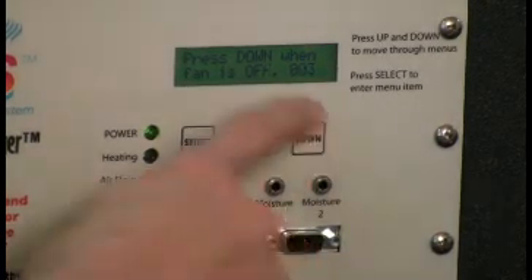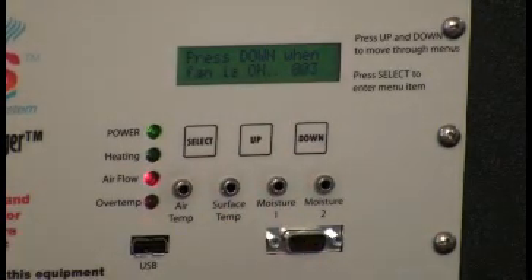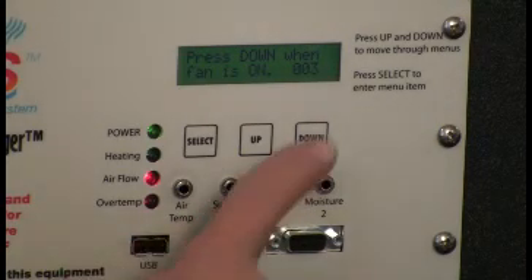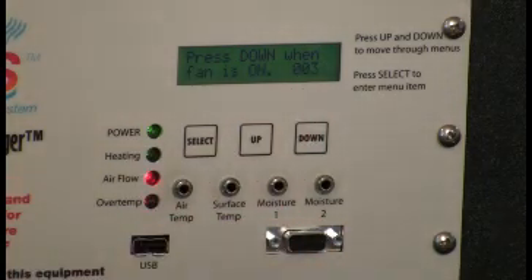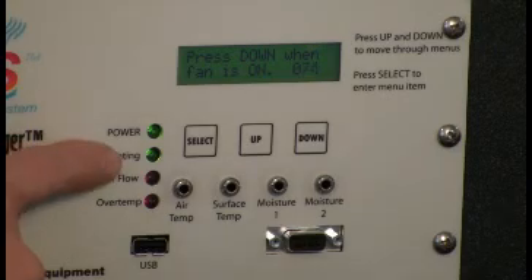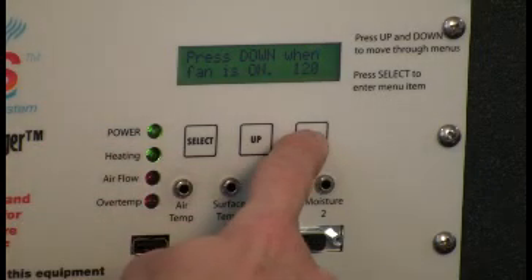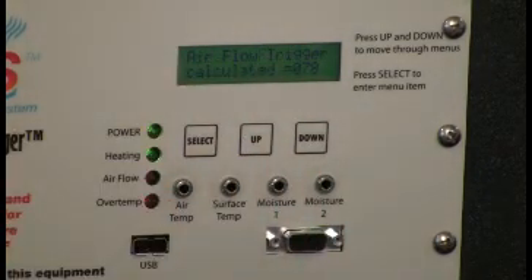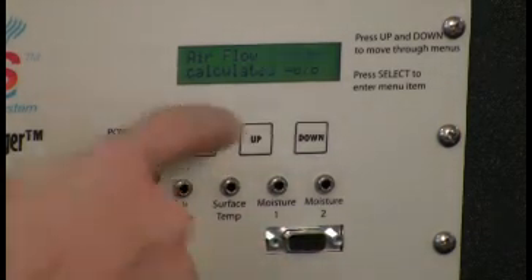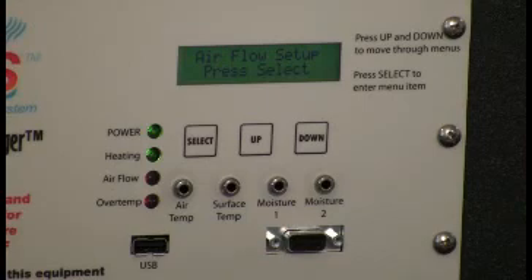Now we will press down to enter the low setting. Now we will turn the fan on, and when the fan is up to speed, as you notice, these numbers will start to change. And when the fan gets to the point where the heating light comes on, we will press down and it'll set our trigger point, and we press Select to enter the information. Our airflow sensor is now calibrated.